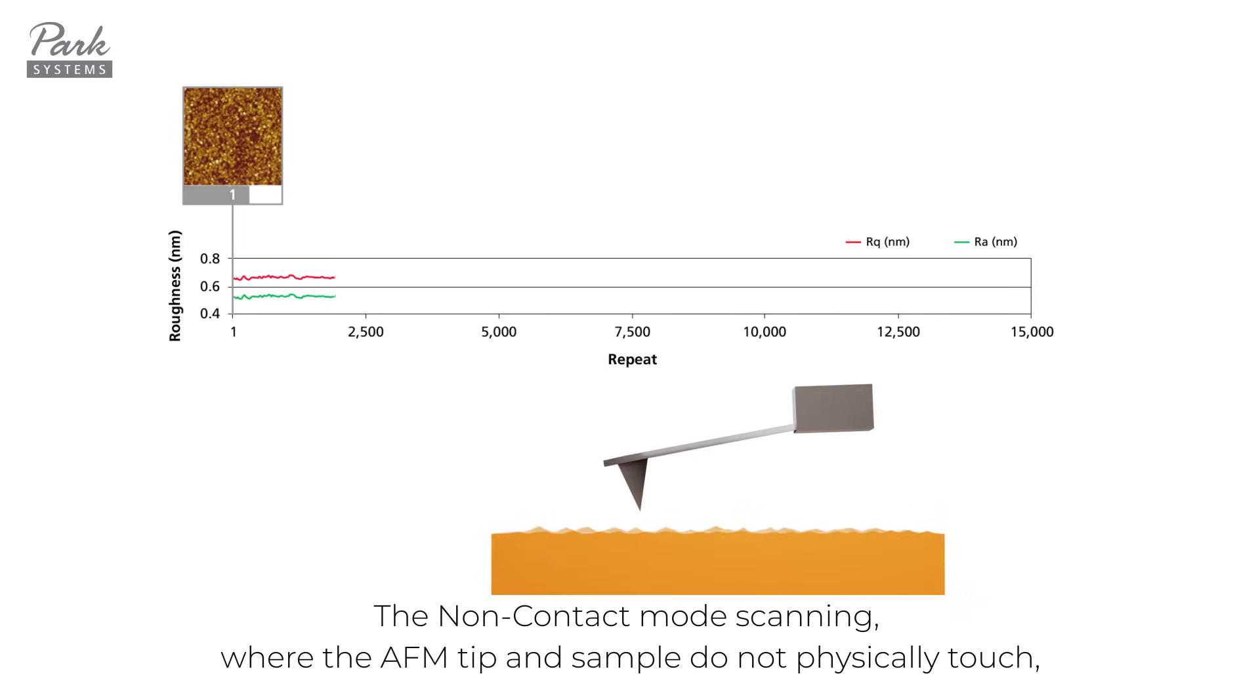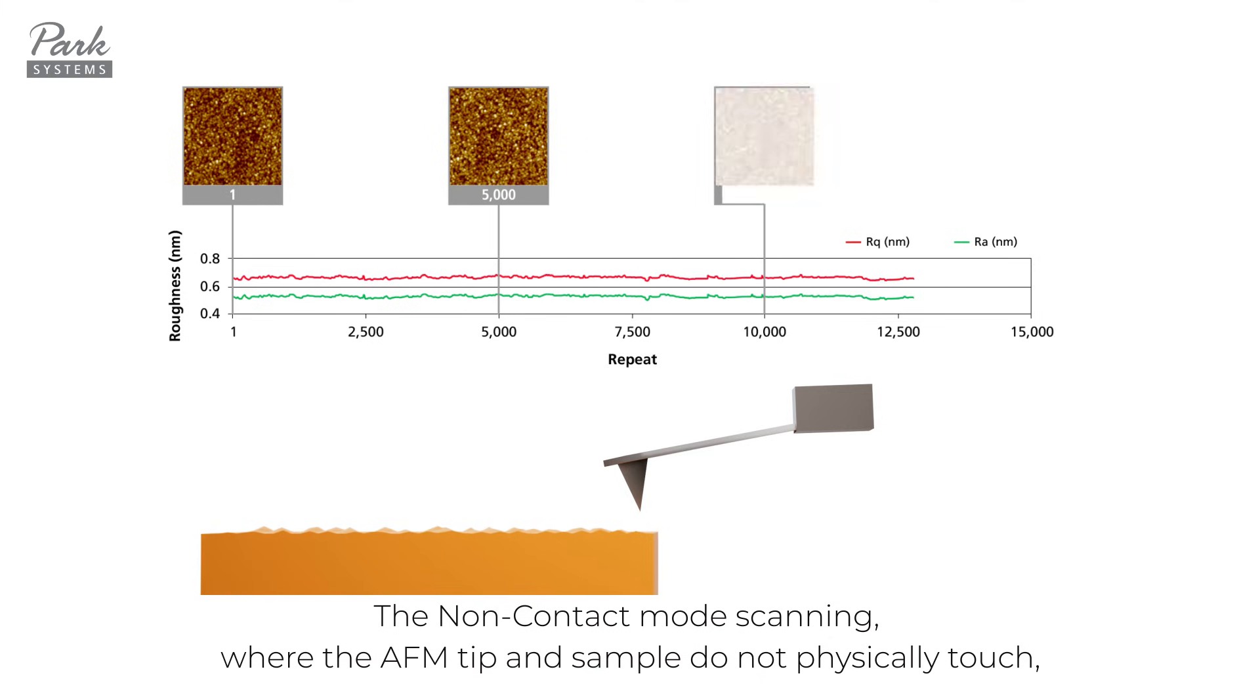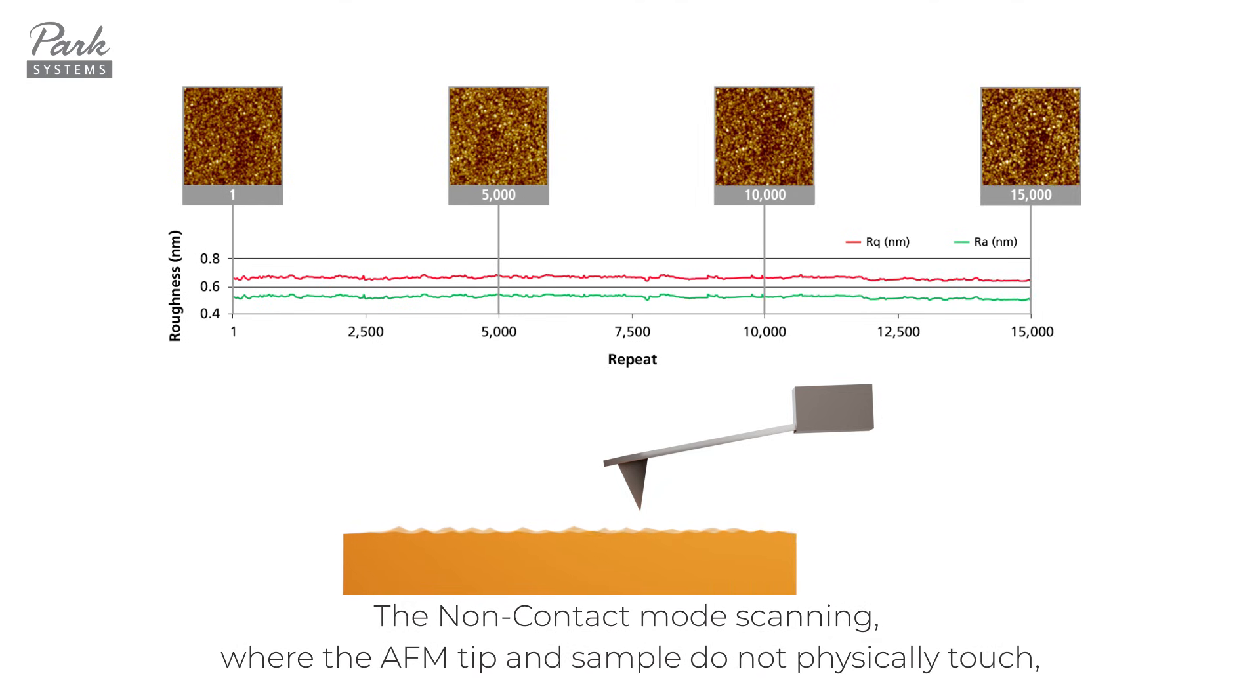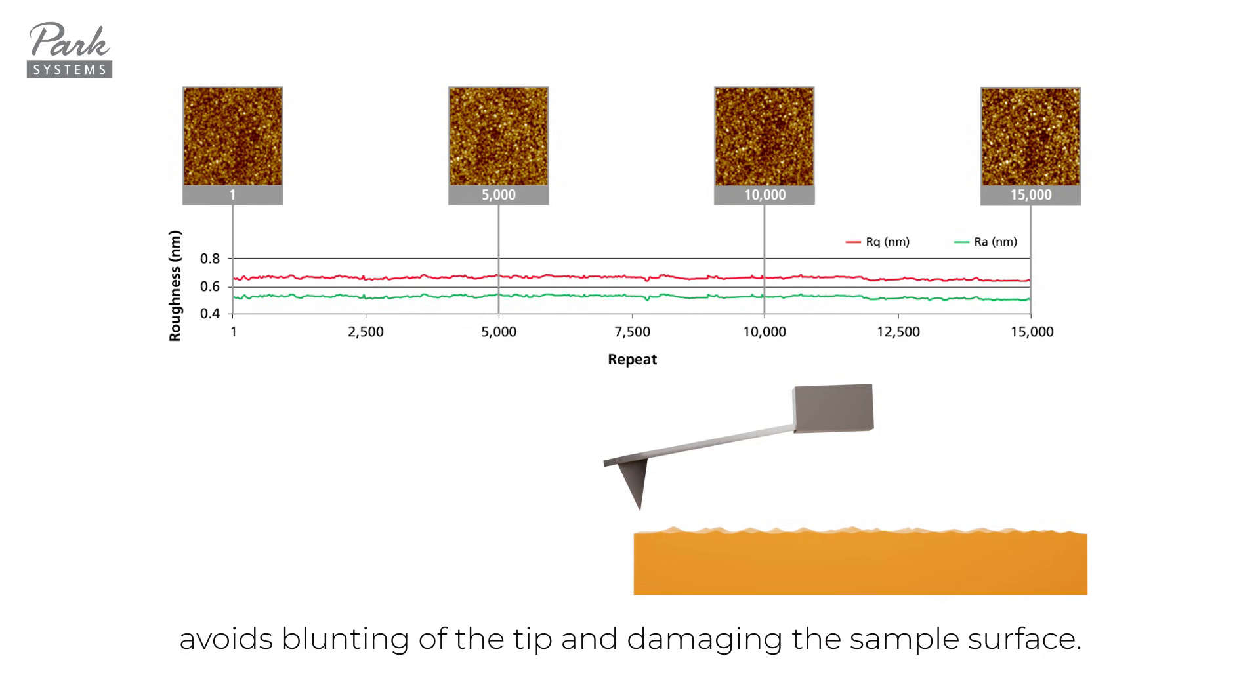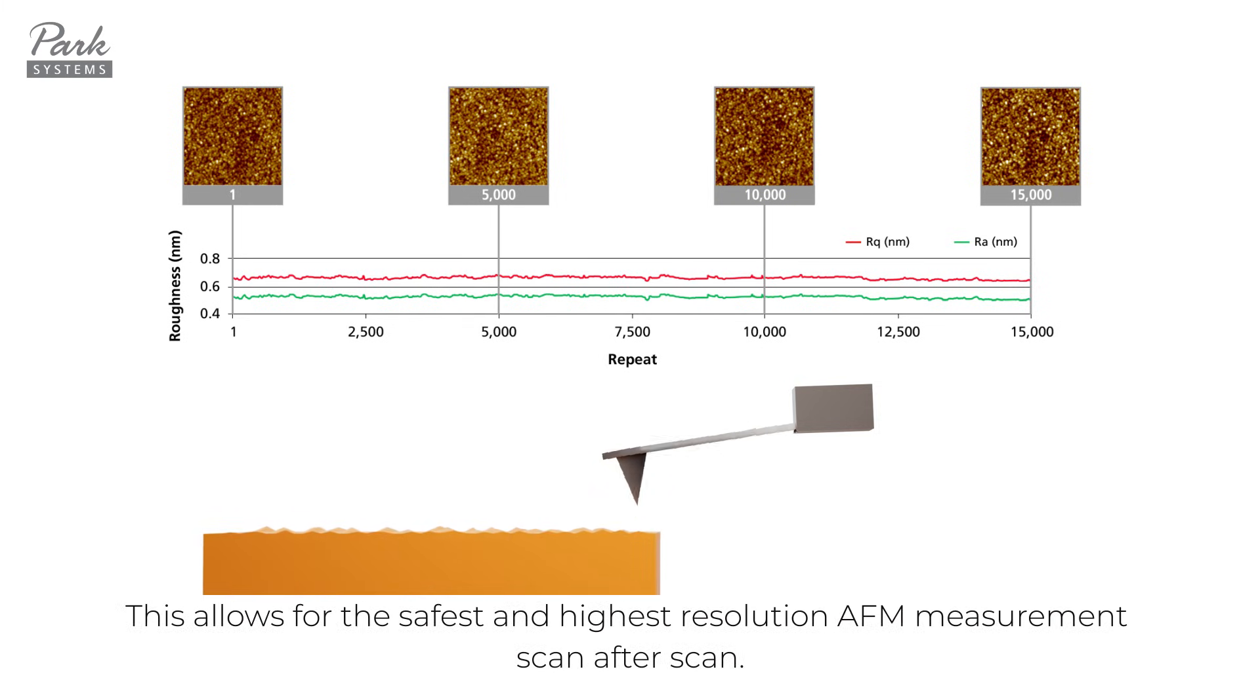The non-contact mode scanning, where the AFM tip and sample do not physically touch, avoids blunting of the tip and damaging the sample surface. This allows for the safest and highest resolution AFM measurements scan after scan.